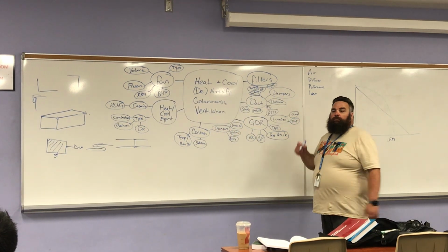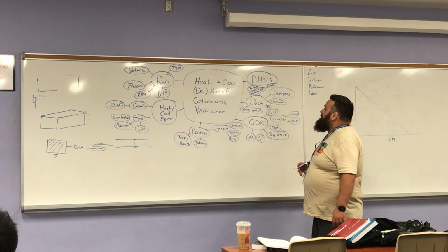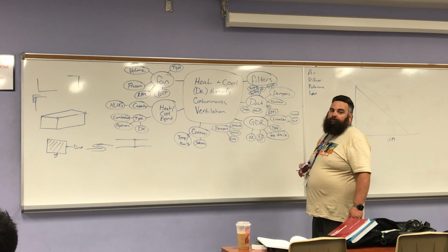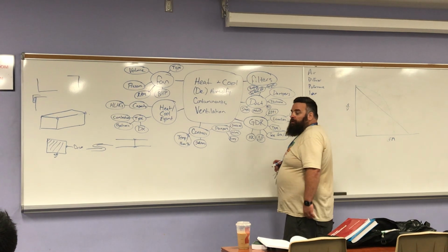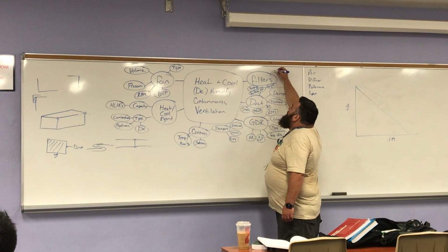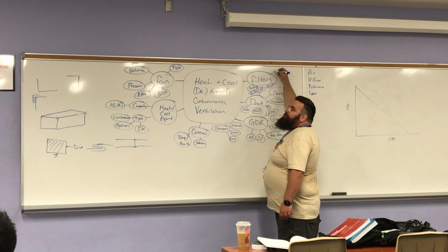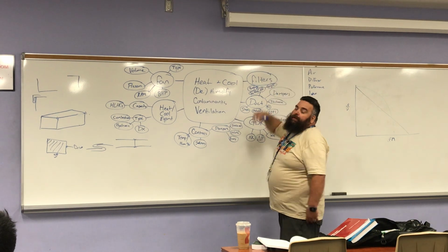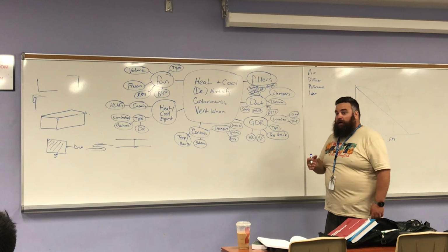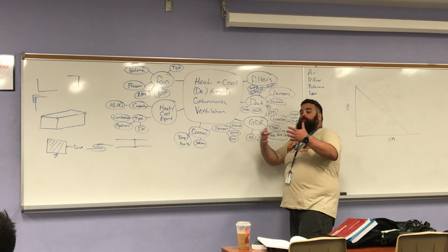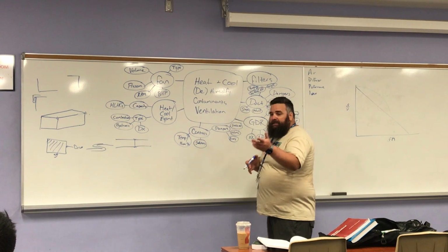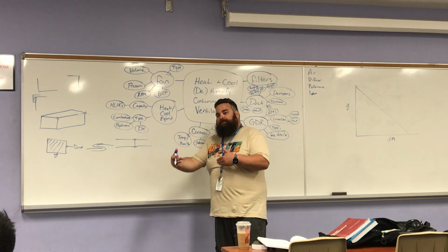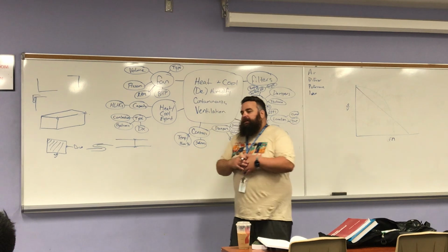Filters. What can we talk about with filters? Thickness? Like size? Yeah, you said thickness or material even. Okay, so the material, because if you have an EAC, you'll need a metal one. I'm not familiar with that. Electric air cleaner. Oh, okay, right. So an electric air cleaner is not actually a filter. It uses electrostatic charge. But it does have those metal grills in it. It does, but we distinguish that differently from a filter. It's a completely different mechanism.